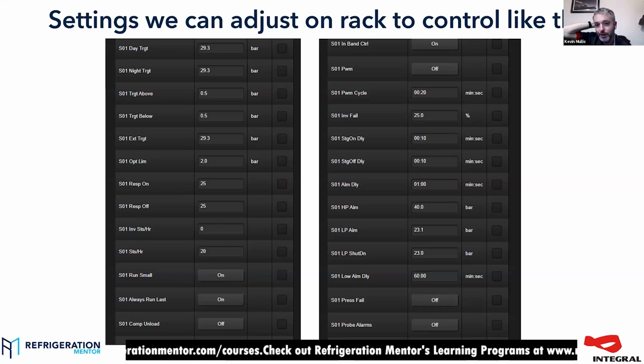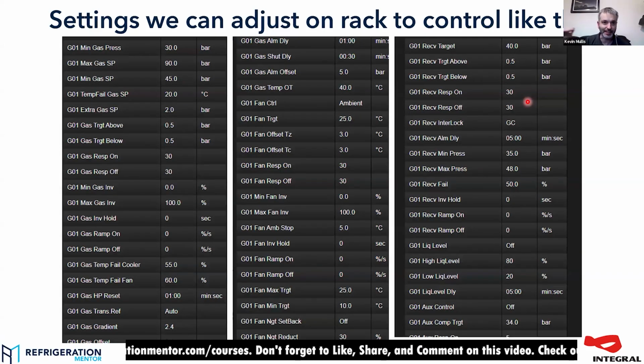That's true. And it's especially important to keep things like the MT stage running. If you've got a dual temperature rack, you've got to run the medium temp compressors to keep the low temp compressors running. And if you've got virtually no medium temp duty, but you need to run the LTs, but it's just a little bit of duty, your MT compressors can be a lot bigger, and you can easily get out of the window where they're still running. You need to give them the maximum opportunity to stay running, because the moment they stop, the LT discharge pressure, especially if you haven't got much MT load, is going to go way up, and then you're going to get unstable.